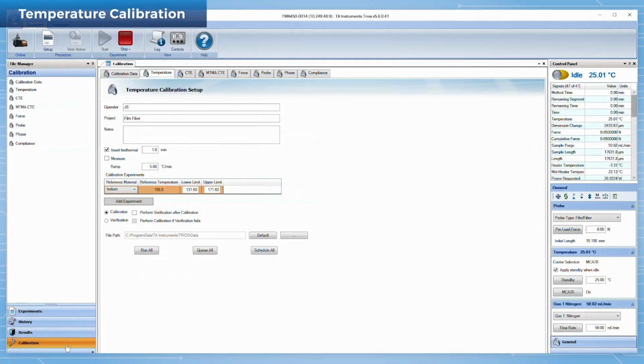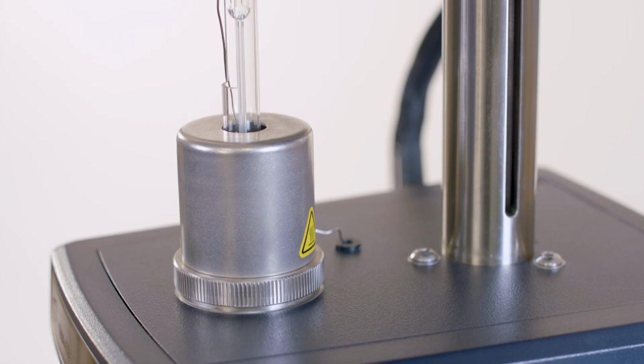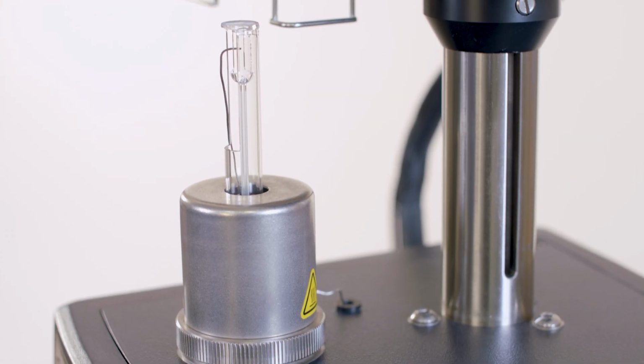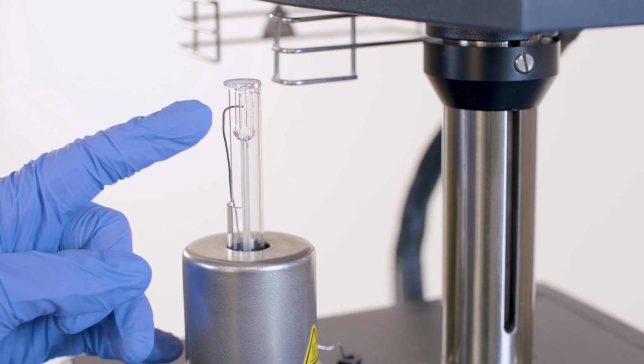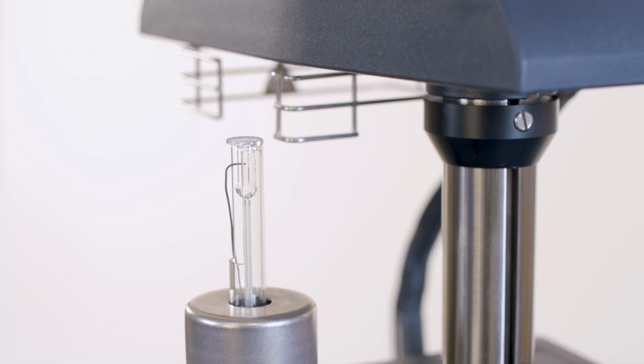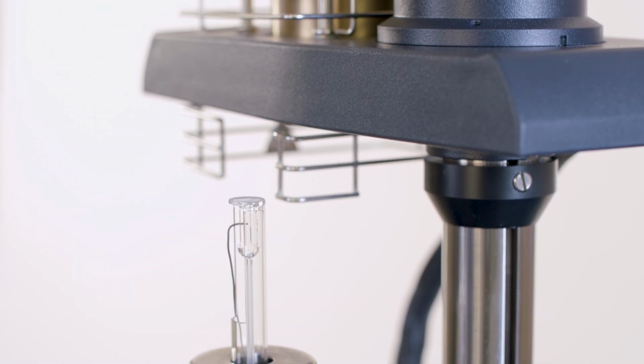The temperature calibration is based on a run in which a temperature standard is heated through its melting point. First, verify the thermocouple position. For the film fiber accessory, position the thermocouple tip so that it is at the middle of the sample length.